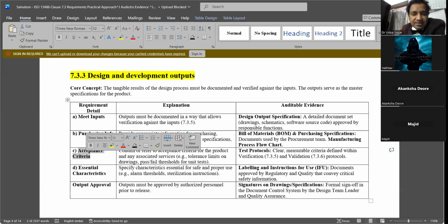Mainly look at some of the parameters that have impact on safety and performance. Because in your design planning, or mainly in the design inputs, you will categorize what parameters have high impact on device performance and safety, medium impact, low impact, and perhaps some have no impact also. So you need to grade those parameters and see that the high impact and medium impact ones are very close during verification. But your story in R&D doesn't end there, where input and output are matching and verification is done.